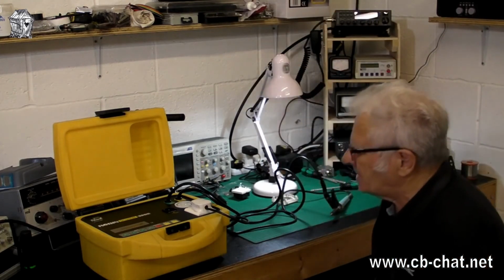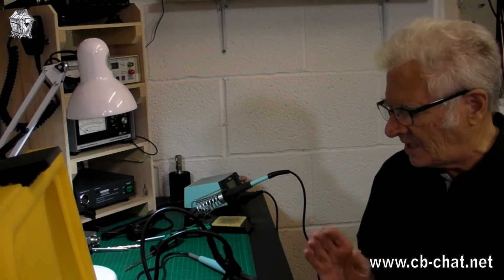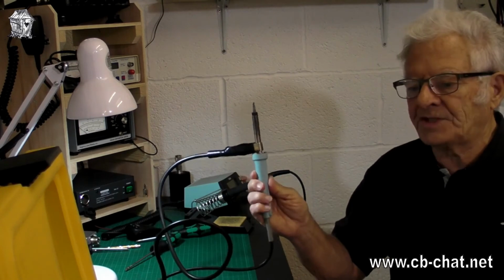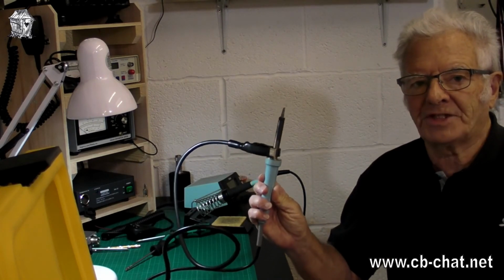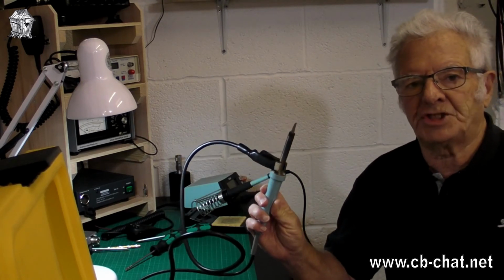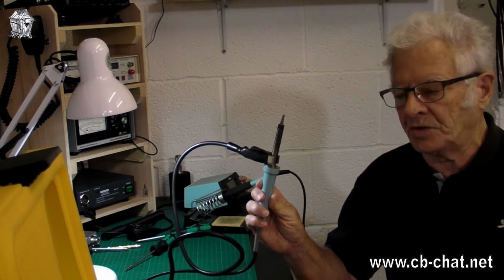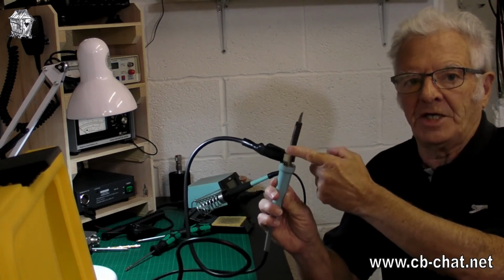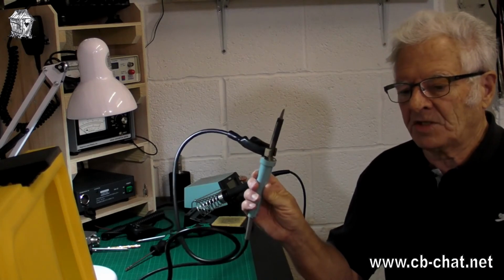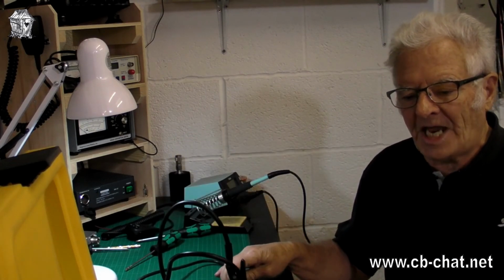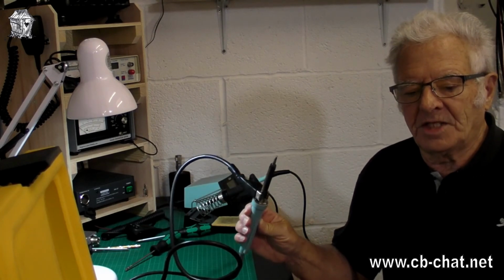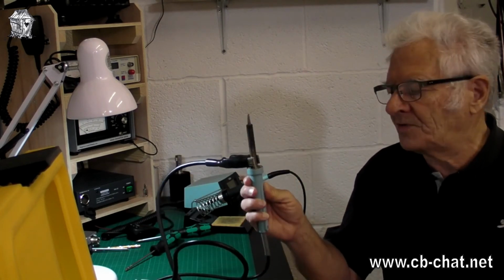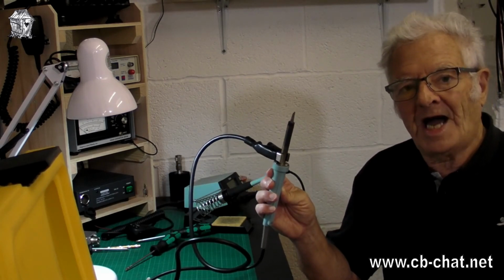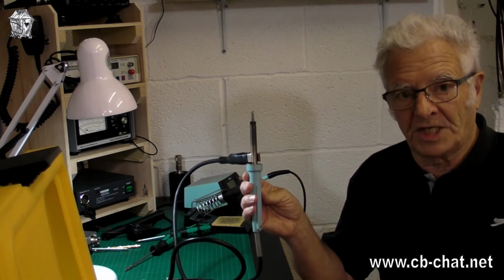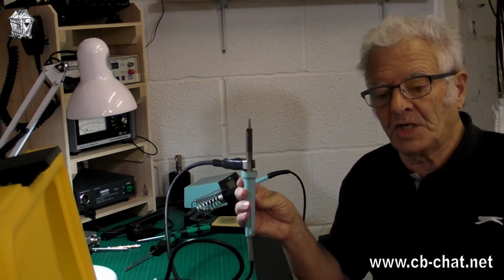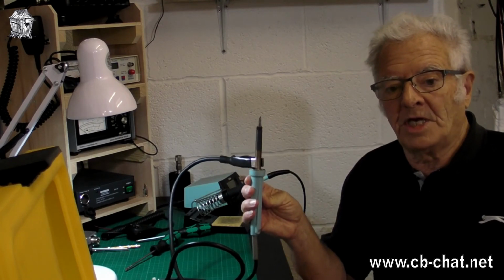So there we are. It tests all the tests that there are. So the actual metal of this device is well and truly earthed at less than the test value. With the rules and regulations, it's got to be less than 0.25 of an ohm to ground the metal of any object that's got metal on it, say a toaster or whatever. So there we are. So it's passed its electrical tests. The insulation is good. The earthing is good. So we can now put a sticker on that to say it's passed. Although it hasn't really, because we've got a 1 amp fuse in it, and that is extremely naughty. It shouldn't be a 1 amp fuse that will blow at 1 amp. It should be a 3 amp fuse.